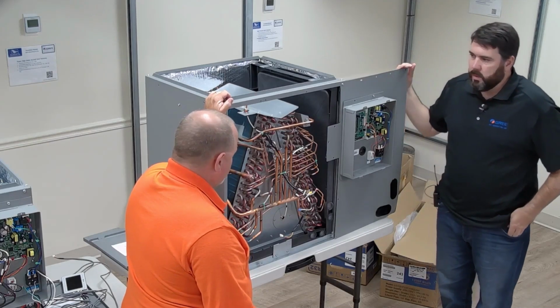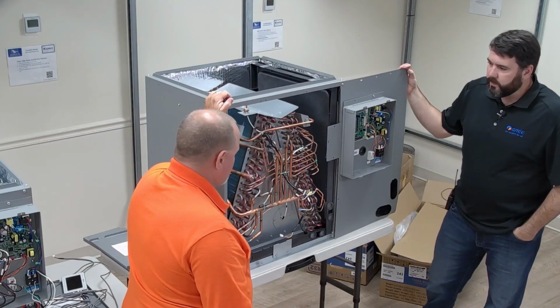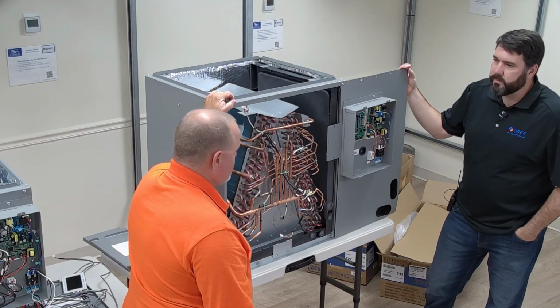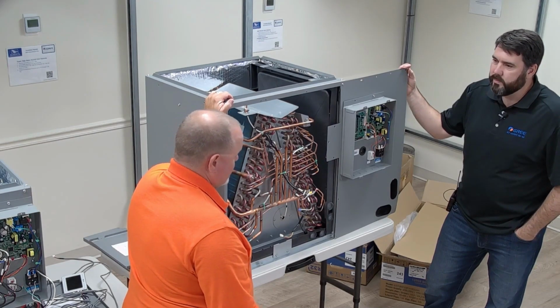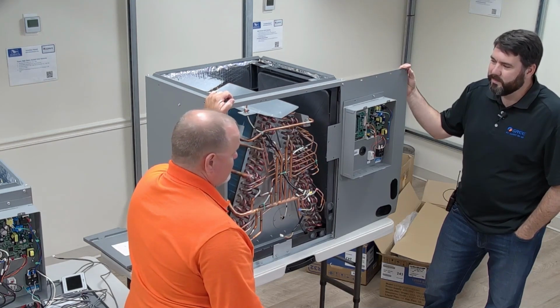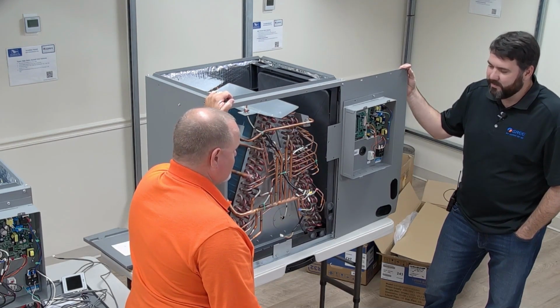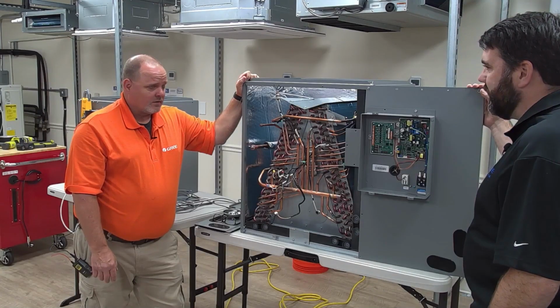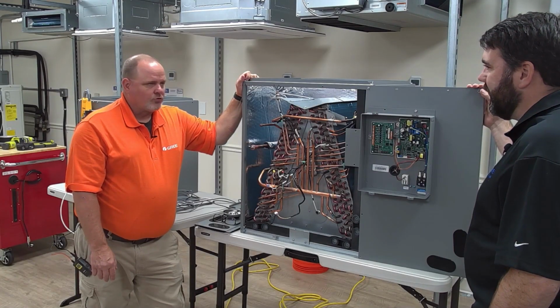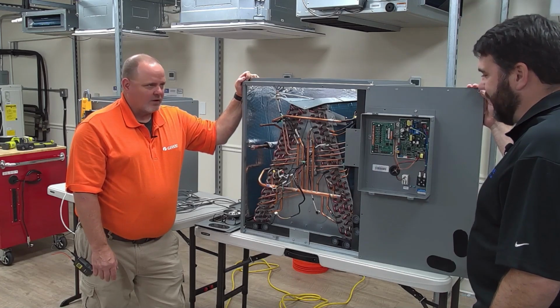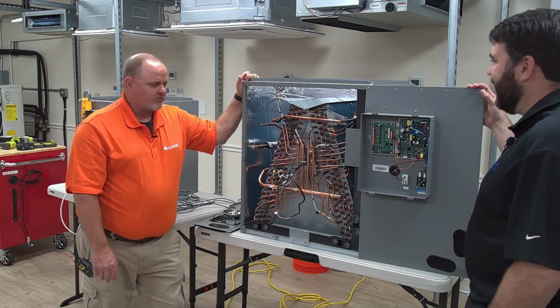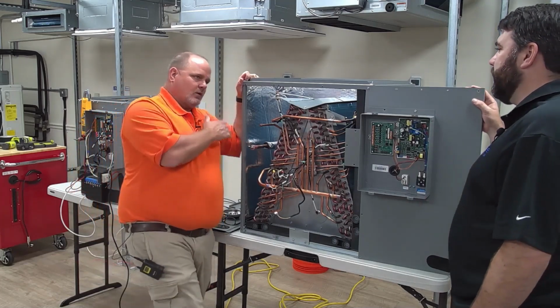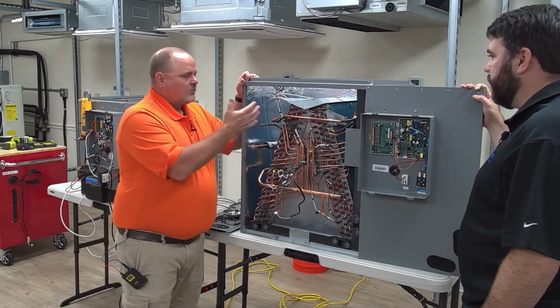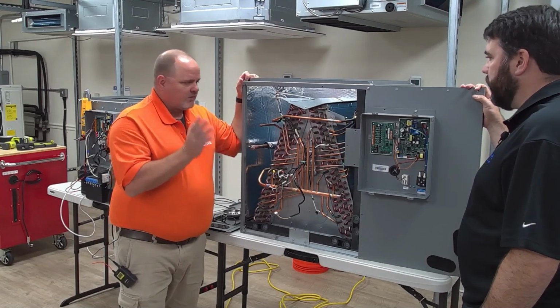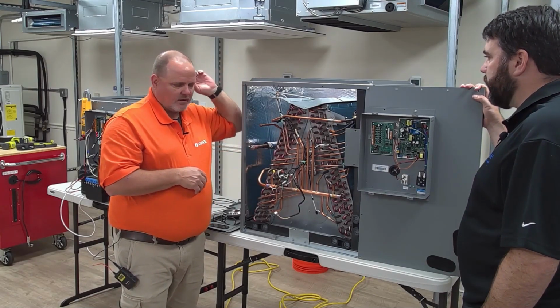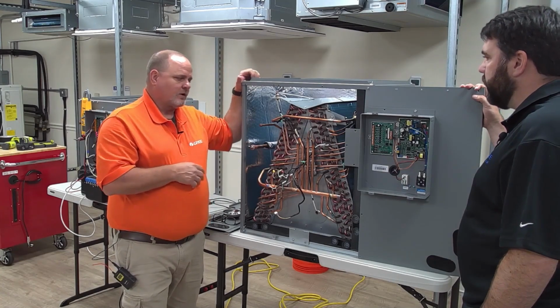Well, and I'll tell you guys, and I've said it for years, if you're going to do a horizontal application, most likely you're taking that up into an attic or into the crawl space. You rarely do that inside a house where you can stand comfortably and do it. Make sure you do that before you take it up into the attic or the crawl space. Know which way you're going to be laying that coil, on the left side or the right side. Move that drain pan over and get all that done before you ever take it down in the crawl space or attic. It'd be so much easier.